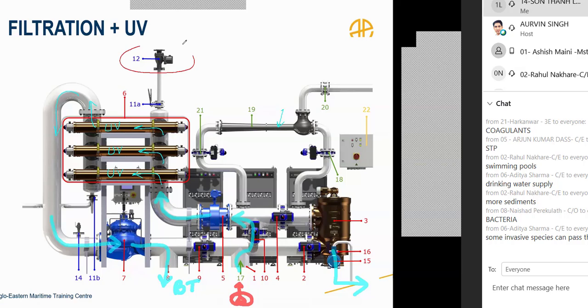First of all, we must know what these valves 11A and 12A are. Why are 11A and 12A fitted on the inlet header? 12A is your auto venting valve. Basically it is removing air from the system inlet. And for this auto vent valve to work, 11A is normally open, always. Or you can say locked open.